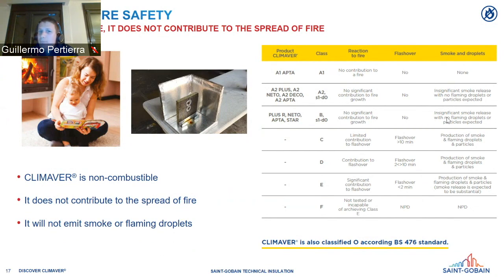We also have different products with different classes in CLIMAVER. The minimum is PLUS, NETO, APTA, STAR, which are class B S1 D0. But if you require better performance in terms of fire reaction, we have the A2 products, like A2 Plus, A2 Neto, and A2 Apta. And we have a 14 millimeter thickness product that is A1, the best class in the Euro class — meaning no contribution to fire at all.